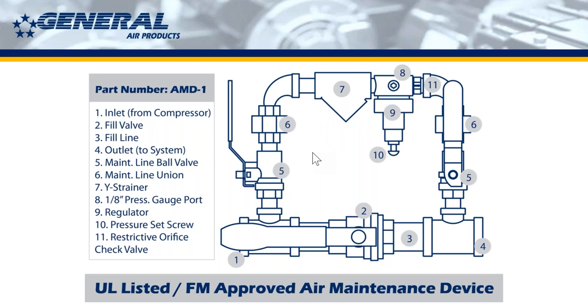That's important to understand. Again, a question we get from time to time is that the air maintenance device or the compressor isn't meeting the 30-minute fill-up time. What's wrong with the compressor? And then we come to find out that the compressor is being used to fill the system in 30 minutes with the fill line closed. The fill line must be open in the orientation that you're shown here. And then once you get up to your 30-minute fill and you get your 40 PSI in 30 minutes, you then close that fill line and open the regulator line, so that the air goes from the compressor through the Y strainer and into the air regulator and then out into the system.